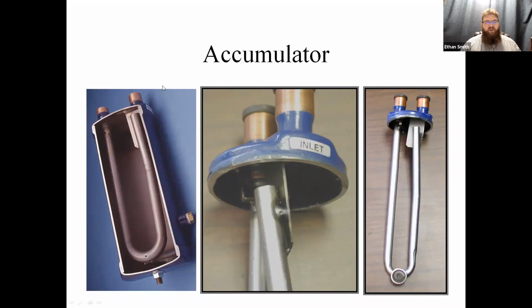When that happens, all the oil that goes out of the compressor winds up in the accumulator. And so what I'm talking about when we do a torch test is you take a torch and you very slowly draw it up the side of the accumulator just to put some heat into the wall. And then with the back side of your hand, start at the bottom of the accumulator very carefully so you don't burn yourself, and just touch the side of the accumulator where you ran the torch. What you'll find is, in a properly operating accumulator, the temperature will change dramatically after about 2 inches on the bottom of that accumulator.